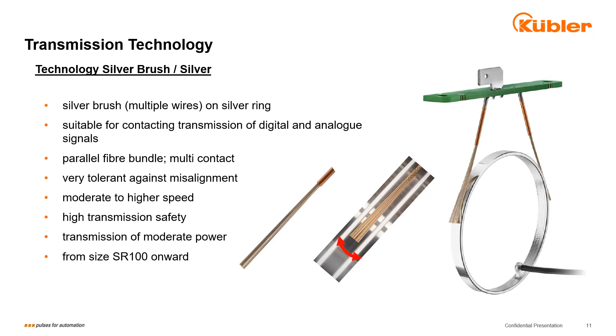Here we see another version of silver-silver technology, which is more used in bigger slip rings. The brush is made of a bundle of single silver wires spreading out when touching the silver-coated ring. With this technology we instantly receive multiple contact points and secure a very stable and robust contact. The contact pressure is minimized and therefore we achieve a big lifespan. In many cases the slip ring competes with the lifetime of the machine, and the produced wear debris can be neglected.